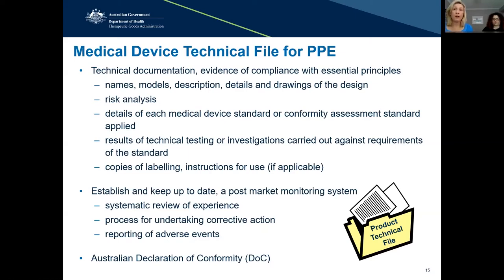Components of the technical file also require the manufacturer to have information about the post-market monitoring system. There needs to be a systematic review of the product to make sure it's continuing to comply with the requirements. The manufacturer needs processes in place for undertaking corrective action, and if something goes wrong with the device, they need to be aware of their responsibilities for reporting adverse events.